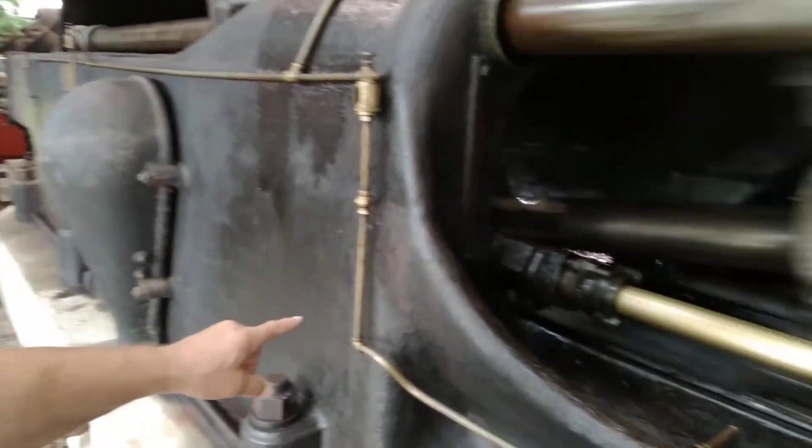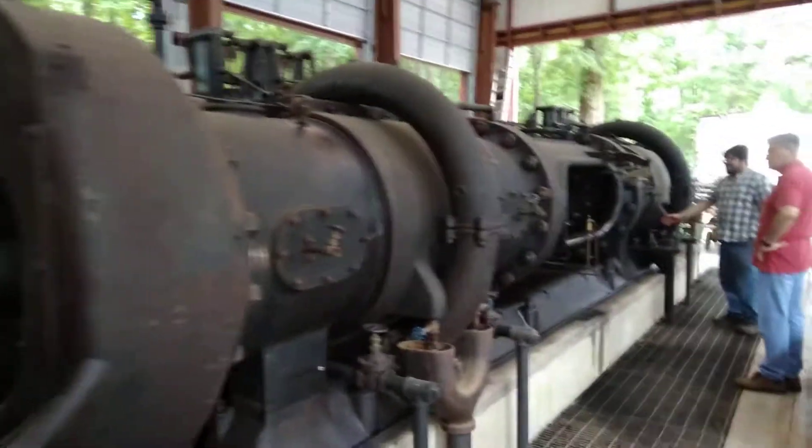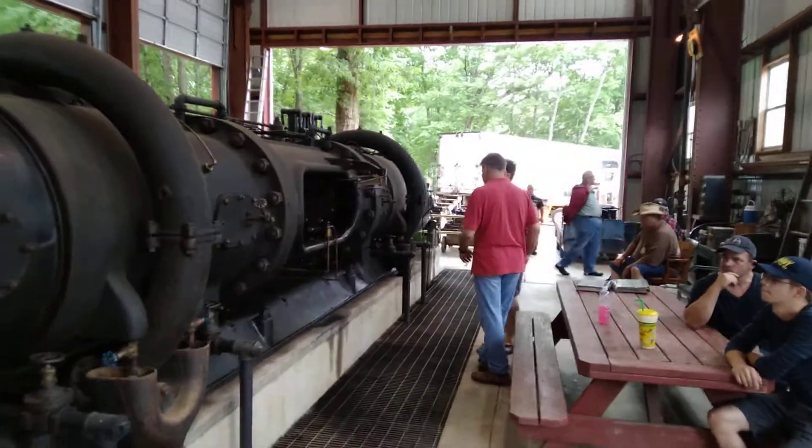This is the trumpet that Jonathan was talking about. The water comes in this valve down here into this assembly. It's fed into the inboard end of the piston rod. The piston rod is 9 inch and it is hollow. The water goes through the piston rod, through a baffle in the piston, to the next section of the piston rod, through the next piston, and out the tail end — you saw it dumping out at the other end.